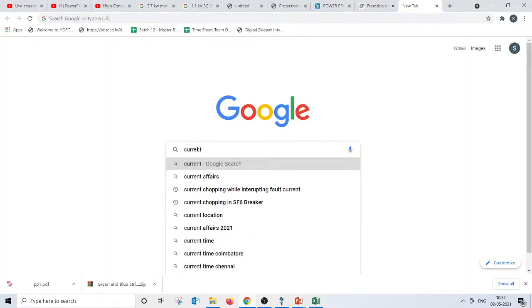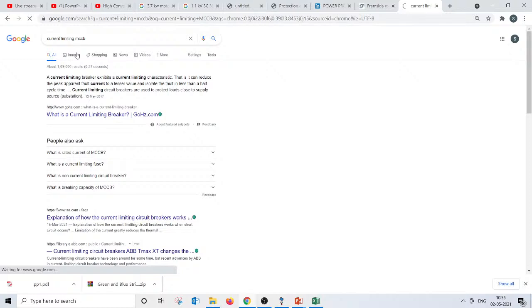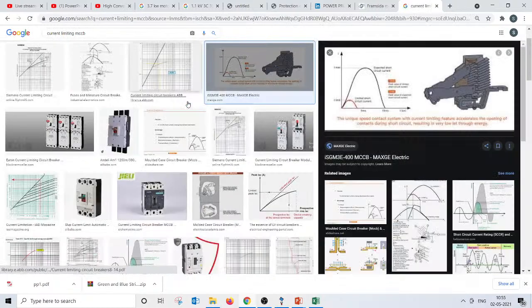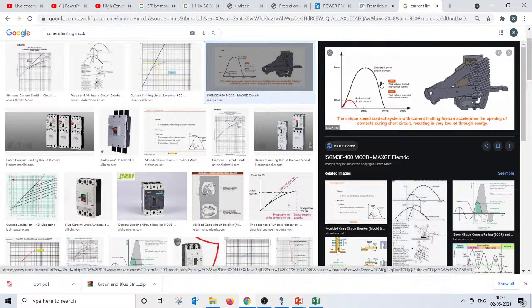I guess in our video on short circuit we have also talked about this. Right, you will get quite a lot of things, and let me put it in an image so that it will be easy for you to understand. Right, this is a typical example. This is the expected fault current, the sinusoidal, and if you have current limiting features, this curtails the fault current in less than 2-3 milliseconds. And you may not reach even the maximum fault current. If you have current limiting type MCCBs in the outgoing feeders, then the coordination is not to be done with ETAP. You need to take the manufacturer's simulation software or some other charts to validate the coordination. Even if an MCCB is available, you need to ensure that it is properly coordinated.